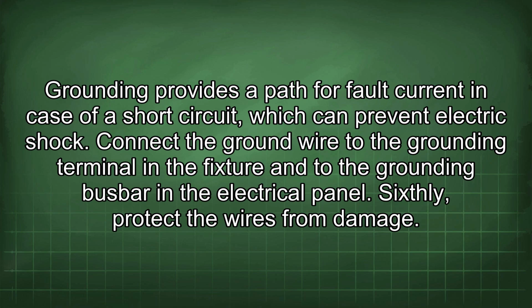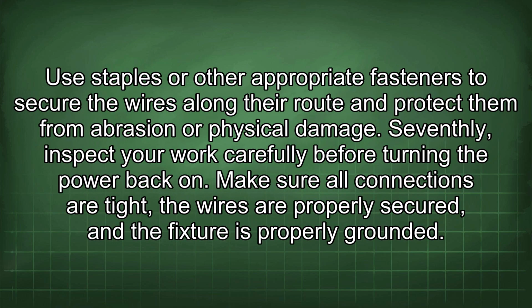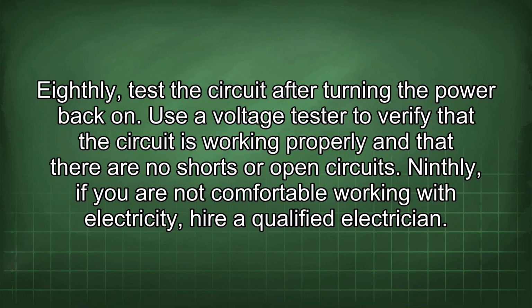Sixthly, protect the wires from damage. Use staples or other appropriate fasteners to secure the wires along their route and protect them from abrasion or physical damage. Seventhly, inspect your work carefully before turning the power back on. Make sure all connections are tight, the wires are properly secured, and the fixture is properly grounded. Eighthly, test the circuit after turning the power back on. Use a voltage tester to verify that the circuit is working properly and that there are no shorts or open circuits. Ninthly, if you are not comfortable working with electricity, hire a qualified electrician.